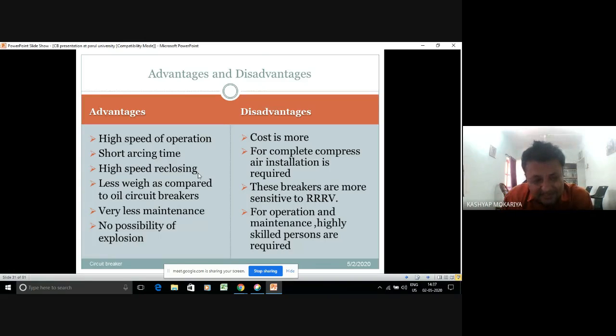Now what happens in this case if your breaker is permanently tripped? Then again you will have a long time to restore it. So your breaker will have 3 or 4 more shots of close-open operation. Say close-open, close-open, close-open, and it will check whether the fault is gone or still existing. If the fault has already cleared, then it will permanently close the breaker. If after those 3 cycles of operation the fault is still persisting, then the breaker will assume that something bad has happened. It is not a transient fault. It is not a fault like a bird sitting on the line, or a tree fallen on it. So this is a typical case where reclosers are used.